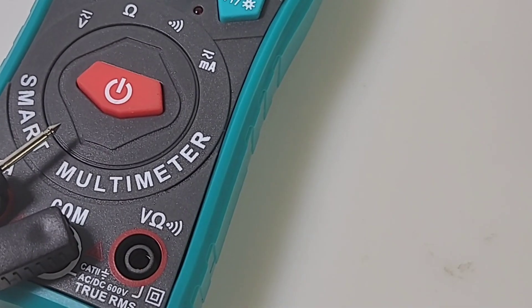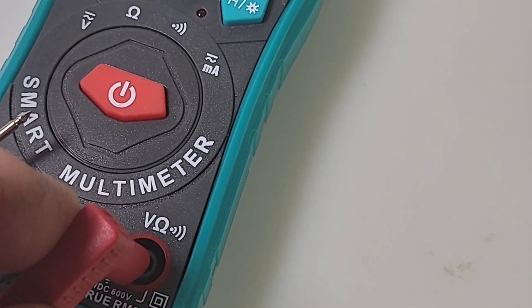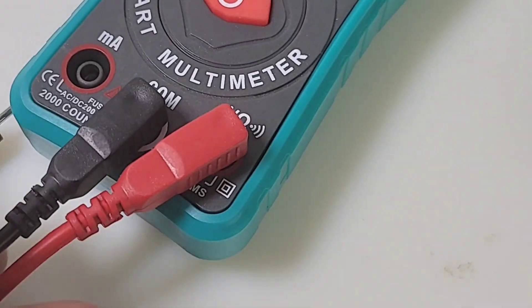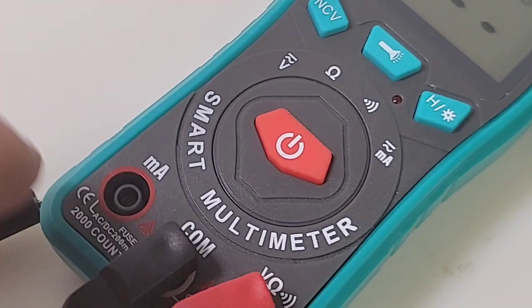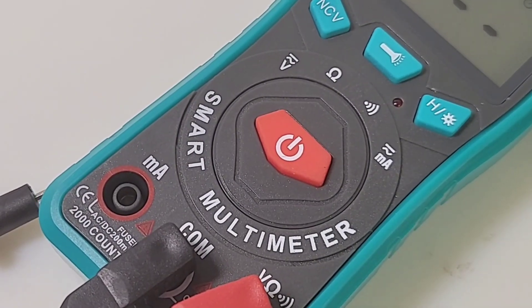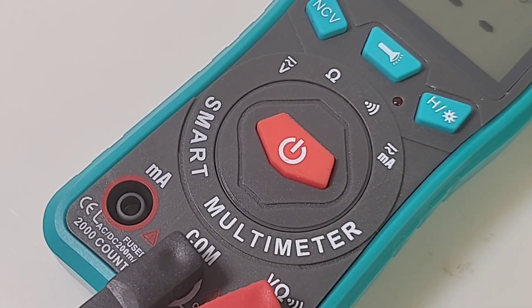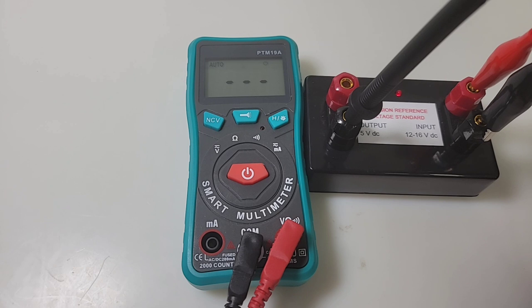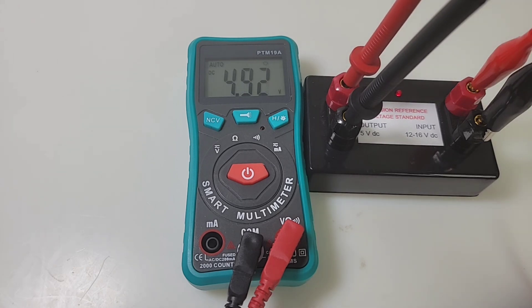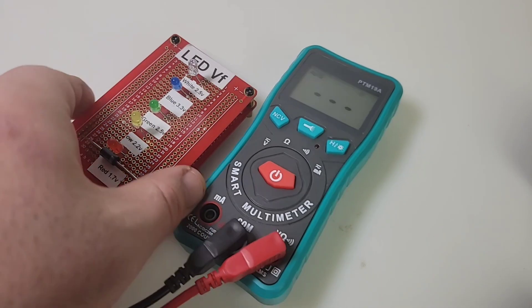Test leads fit in just like so, nice and snug, like a bug on a rug. Something like that. Okay, so there they are in there. They're not going anywhere. Let's start off with a DC voltage precision. All right, DC 5.0 volts is what we want. And 4.99, 4.99.